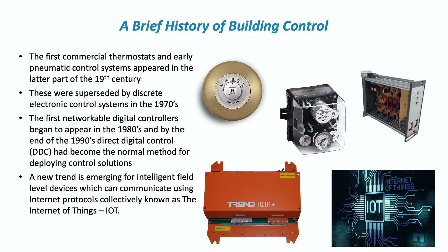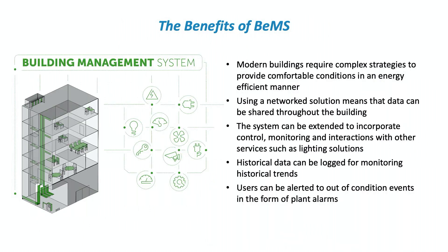More recently we've seen the phrase IoT — the Internet of Things. The difference between IoT technology and standard BEMS technology is that the intelligence to control sits down at the field level and devices can communicate directly with the internet rather than needing a gateway controller. Devices can publish their information direct to the web and be used by other devices. This is the latest development of where our industry is moving.